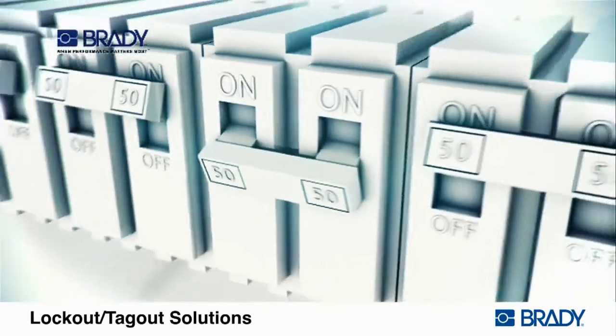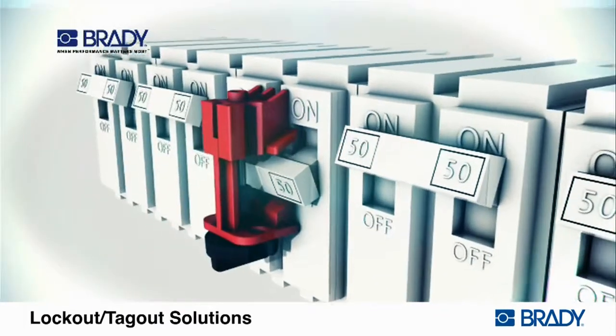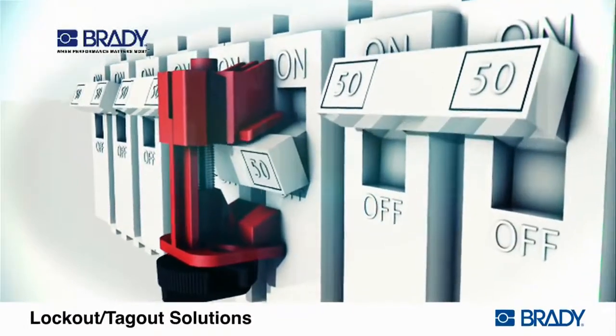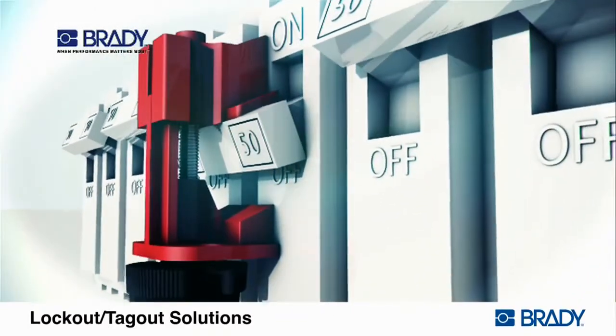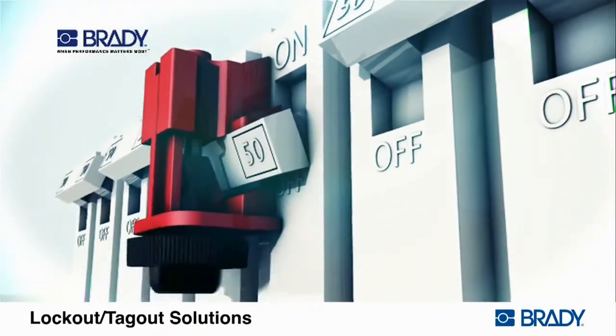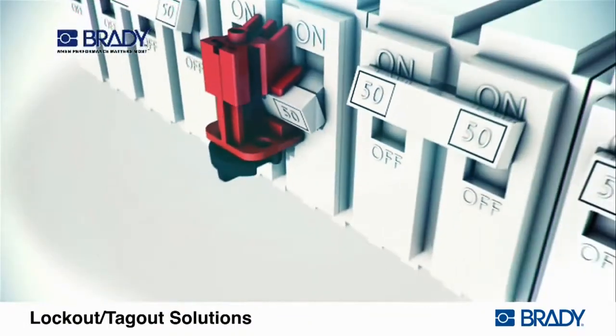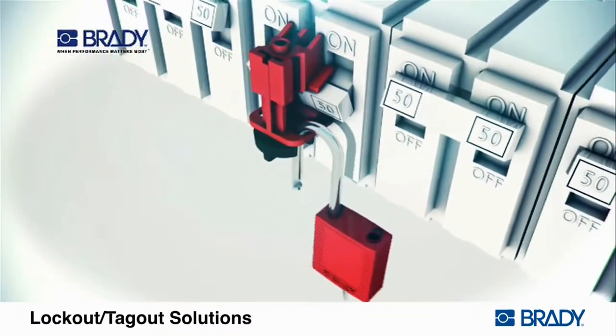Place circuit breaker in the off position. Place the multi-pole lockout device on the circuit breaker tie bar assembly. Rotate the thumb wheel clockwise to secure the lockout device to the circuit breaker. Attach the padlock and worker's protective tag.